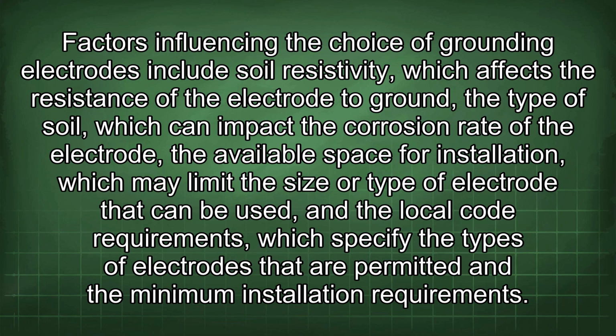Factors influencing the choice of grounding electrodes include soil resistivity, which affects the resistance of the electrode to ground, the type of soil, which can impact the corrosion rate of the electrode, the available space for installation, which may limit the size or type of electrode that can be used, and the local code requirements, which specify the types of electrodes that are permitted and the minimum installation requirements.